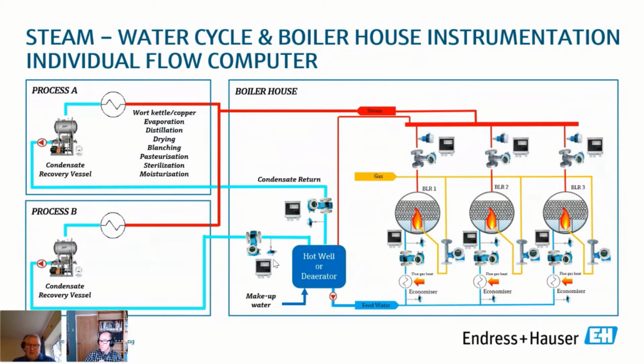I'm looking at the steam water cycle for a simple system - a boiler house with 3 boilers, a steam header, and steam going out to 2 processes in the production area, process A and B. The heat supplied to these processes could be for a range of different applications. The condensate then pushes back under its own vapor pressure to a condensate recovery vessel and gets pumped back into the hot well or deaerator.